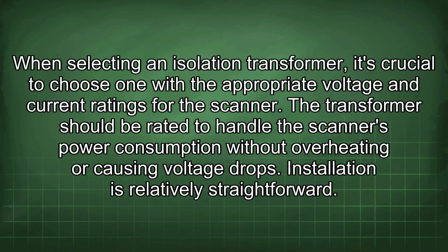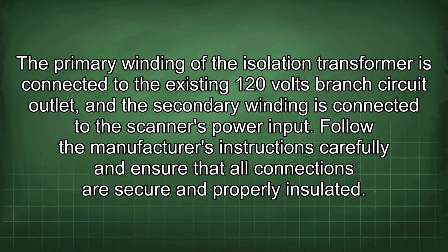When selecting an isolation transformer, it's crucial to choose one with the appropriate voltage and current ratings for the scanner. The transformer should be rated to handle the scanner's power consumption without overheating or causing voltage drops. Installation is relatively straightforward. The primary winding of the isolation transformer is connected to the existing 120 volts branch circuit outlet, and the secondary winding is connected to the scanner's power input. Follow the manufacturer's instructions carefully and ensure that all connections are secure and properly insulated.